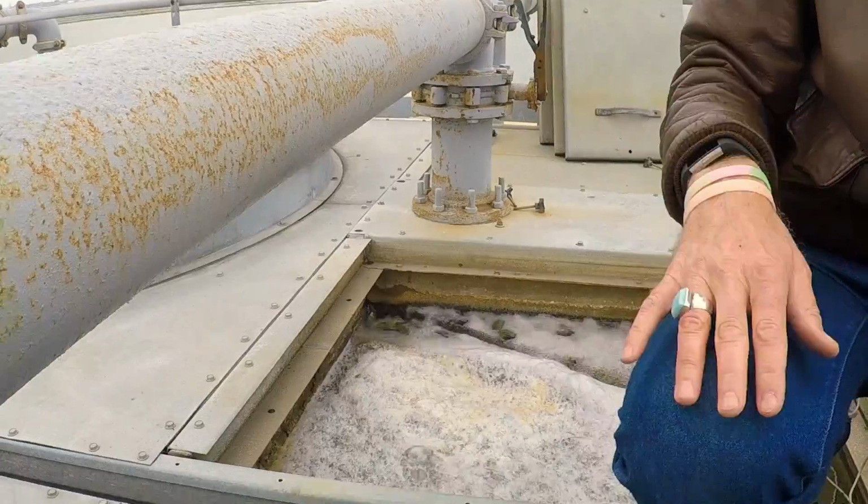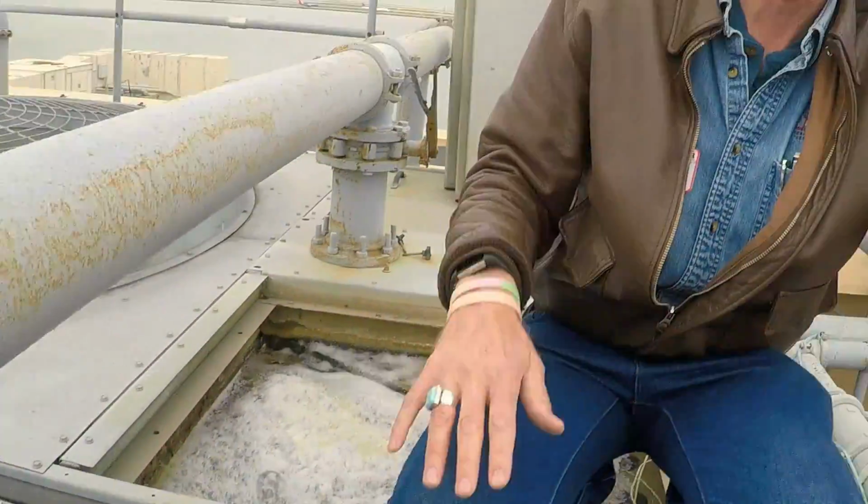Does that make sense? I'm watching people nodding. Yes. Here we go. Okay, so that's the first thing. You can real easily visually tell with a tower that uses nozzles like this if the flow is balanced between the basins just by looking at the depth.